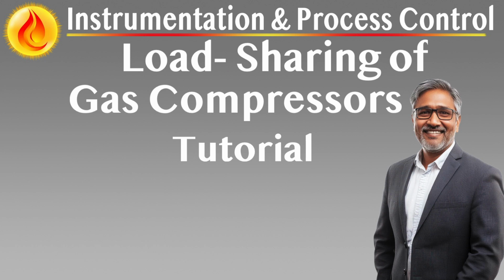Functional structure and control logic. Cold recycle loop components: a dedicated recycle valve connected downstream of the compressor discharge manifold, a shared heat exchanger in the loop to reduce recycled gas temperature, and a cold recycle controller typically configured as a specialized anti-surge control element. Trigger conditions and activation: activated when compressors are nearing a sustained surge region, particularly during process turndown, system transients, and long-duration capacity throttling. Engaged before hot recycle valves, allowing centralized control to stabilize flow network-wide.